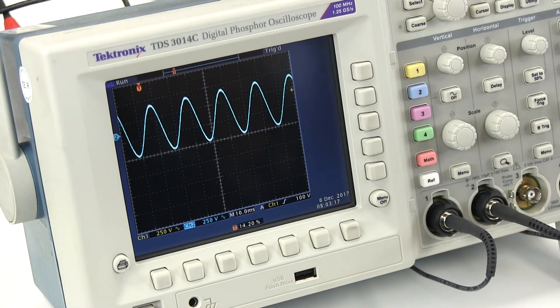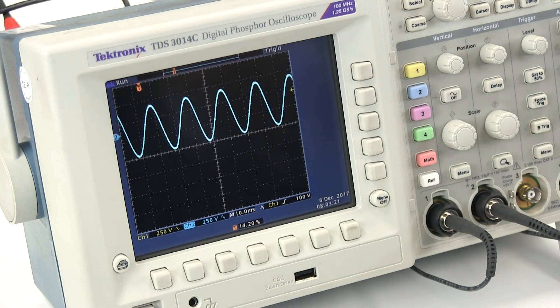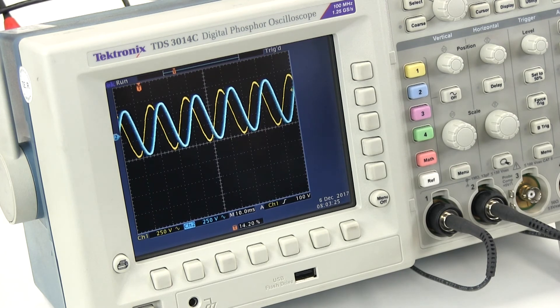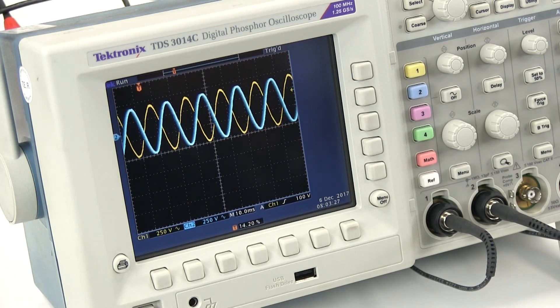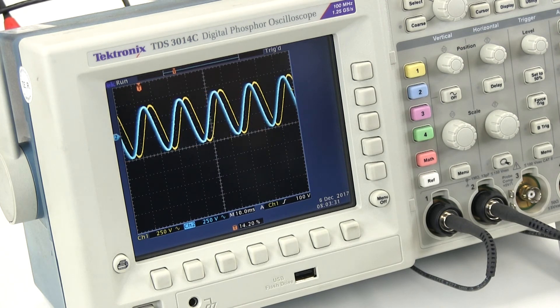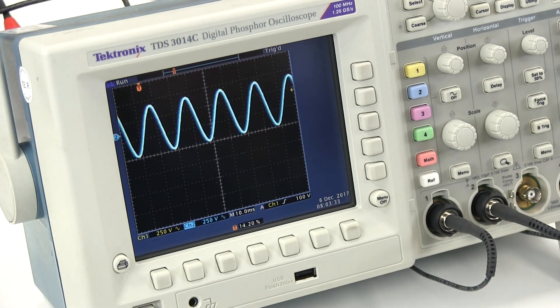Now if I instruct the UPS system to disable the synchronization, you will see that the two waveforms now stray apart. Under these conditions, the input and output are no longer synchronized and hence the bypass line would be unable to transfer instantaneously.